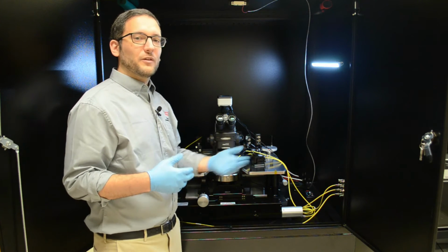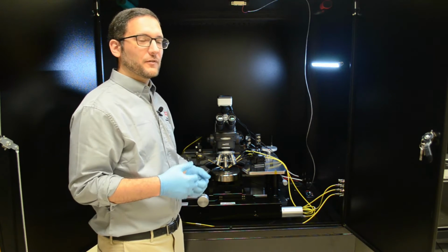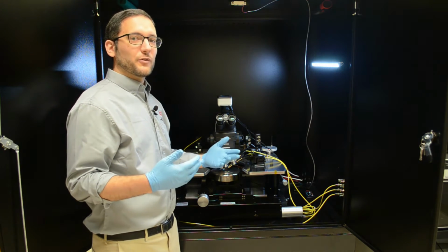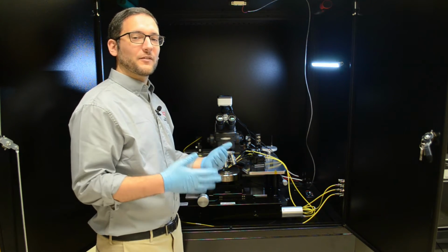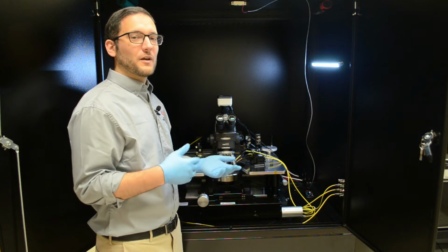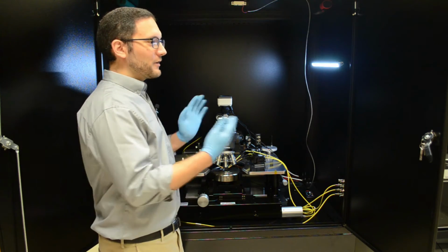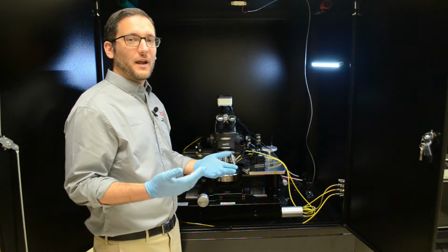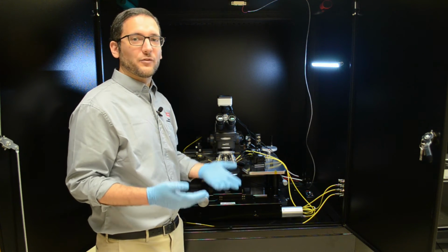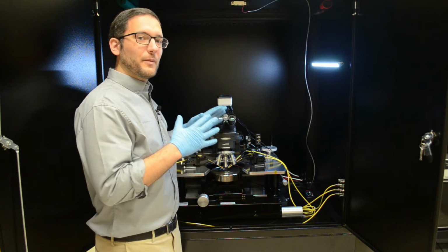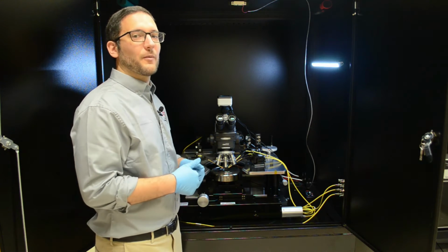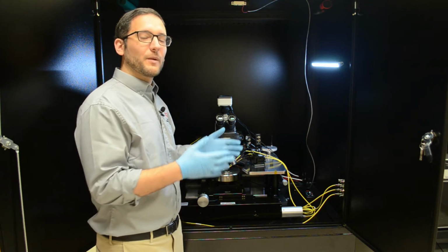I also want to mention a couple things about the enclosure itself. I've already talked about how the enclosure serves a purpose of safety, to keep the operator isolated from the devices and the measurements. There's also a second purpose. This enclosure is also known as a Faraday cage. It's basically a metallic cage or a metal box.